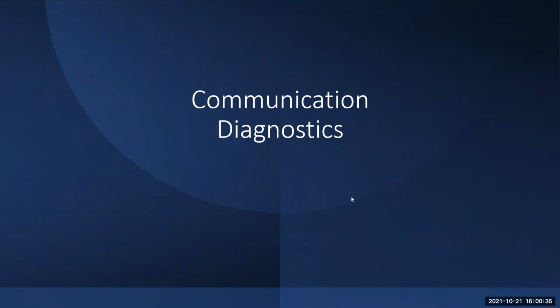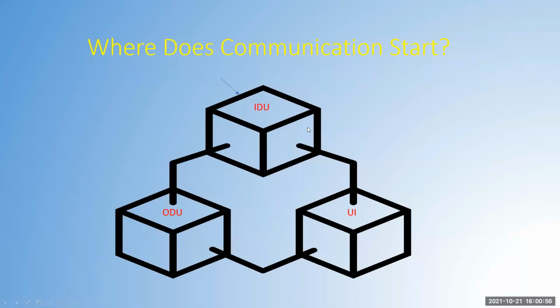Communication diagnostics. This is a big one. We get a ton of phone calls on having indoor outdoor communication errors, equipment not hitting, whatever be the case. We're going to go over that. So where does communication start? It originates out of your IDU, your furnace board, indoor unit board. Then it hits off to your AC heat pump, whatever you got, and then also hits into your UI.